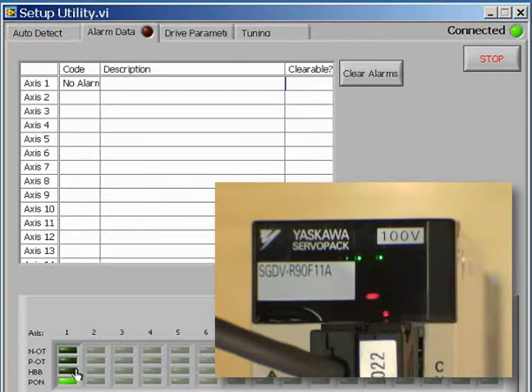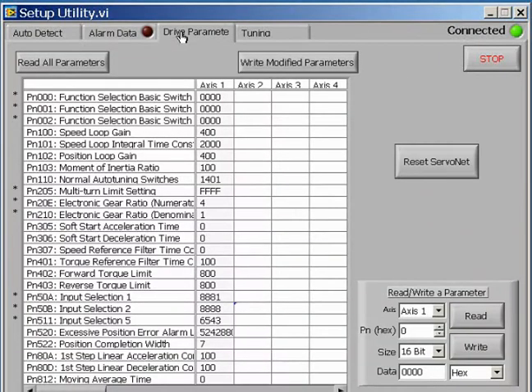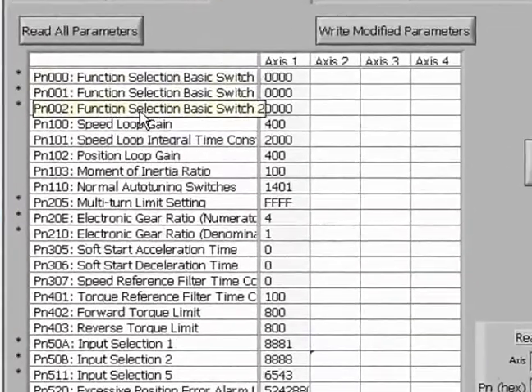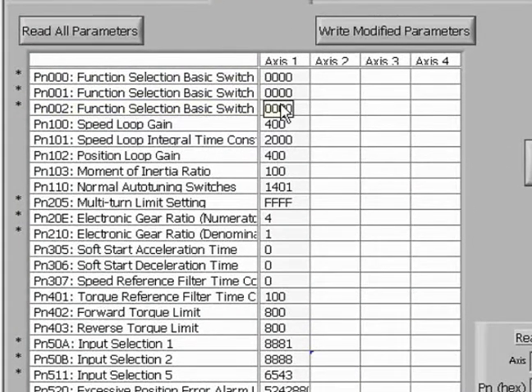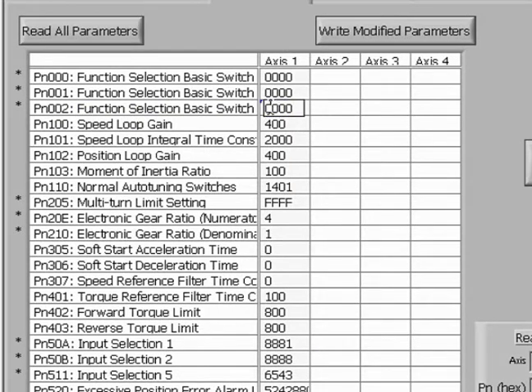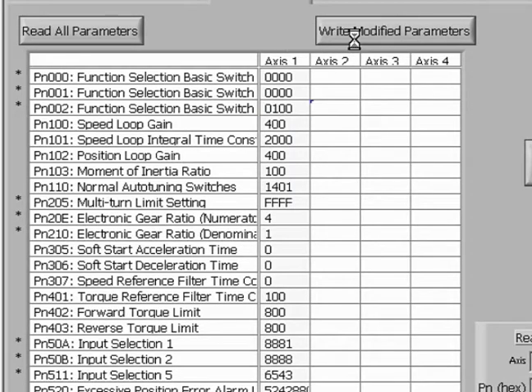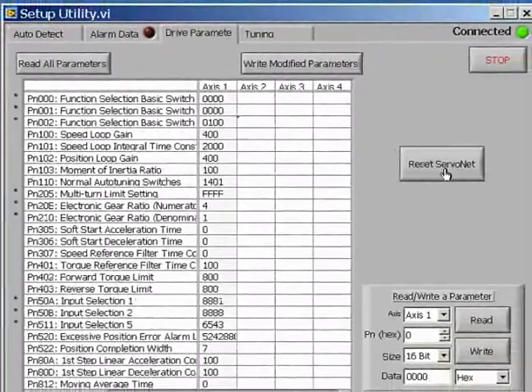The next parameter we will examine is PN002. The setting of 0000 is the software's default setting, which indicates that the drive is configured to work with an absolute encoder. Since we are using an incremental encoder on our servo motor, we need to change this to 0100 by following the same procedures as earlier shown to change and to save this setup.